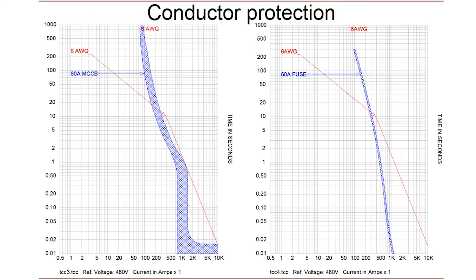We'll look at a couple of examples, starting with a conductor — a building wire. On the time-current curve, in addition to the circuit breaker and fused trip curves, there is a red line representing the thermal damage curve for a number 6 AWG building wire. If the amount of current or duration of the overcurrent reaches that red line, the conductor will be damaged. We want the protective device's curve to stay to the left and below that line. In both graphs shown, the 60A thermomagnetic breaker and 60A fuse are adequately protecting this wire.